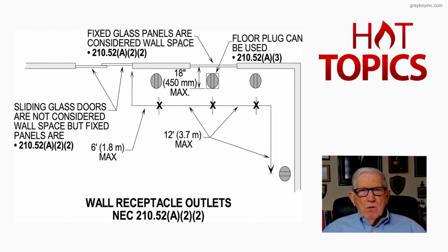And the main thing, always remember, if you're the electrician making the installation, anywhere that you have two receptacles on the wall or anywhere, you should be within 6 foot in the center of them in any direction. If you don't pick up a receptacle, you're too far. You need to move that outlet box closer, even if you have to move into the stud that makes it even closer than 12 foot.